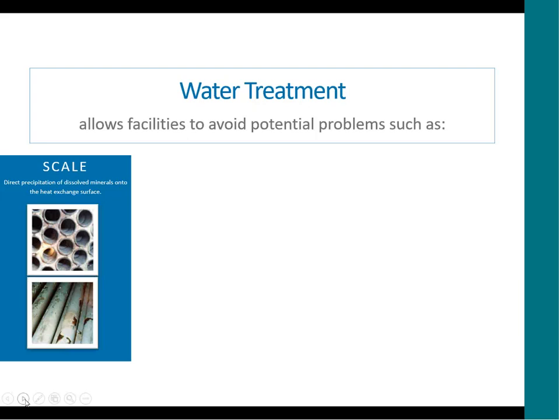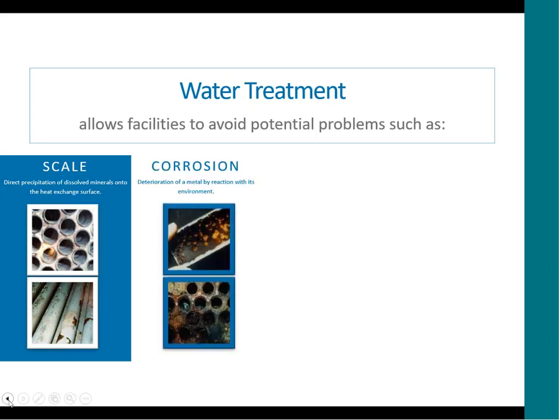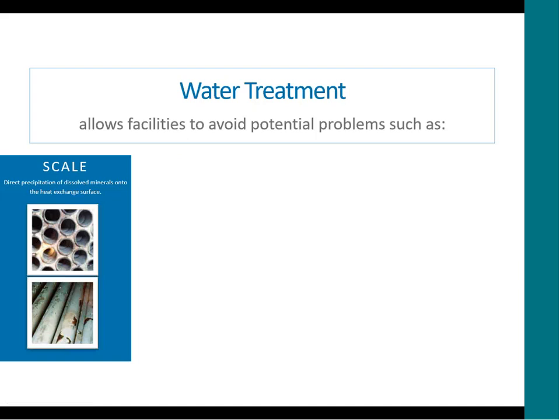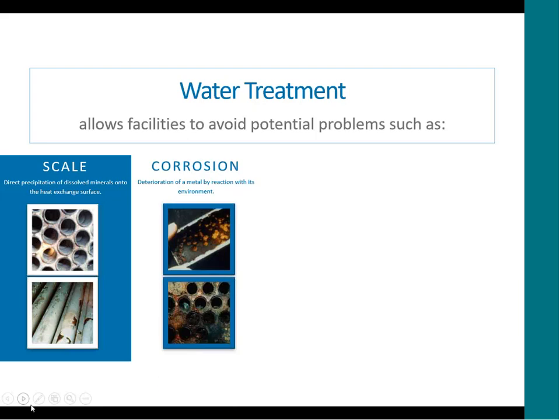So why do we want water treatment? What are we trying to avoid? What problems can occur in our water systems if we don't have a good quality water treatment program? We can have scale. Scale is the precipitation of dissolved materials on a heat exchanger surface. This happens when saturation of the impurities in the water is reached. We talked about evaporation, it's only pure water. We're going to get to a point where the solubility is reached and there's no more room in the water to hold all this dissolved material, so it's going to want to precipitate out onto the system, the heat exchanger surfaces. This is something that we want to control with a good quality water treatment program.